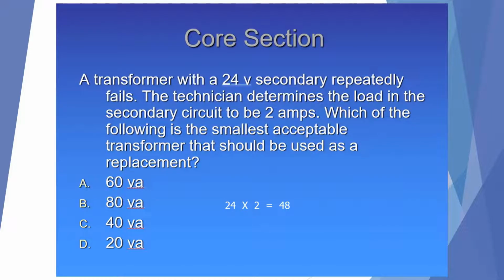In the previous slide, we found how many amps we can work with on a 75 VA transformer. In this question, which was recently seen on the NATE certification test, we can go the other way. If we know how many amps the circuit is drawing, we can determine what size transformer we're going to need to handle that circuit. The question states, a transformer with a 24 volt secondary repeatedly fails. The technician determines the load in the secondary circuit to be 2 amps. Which of the following is the smallest acceptable transformer that should be used as a replacement?